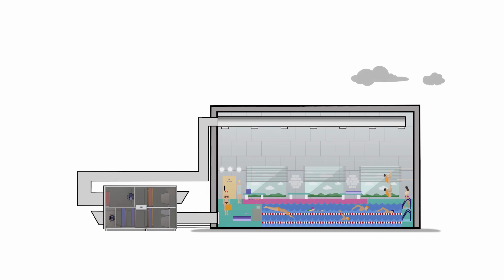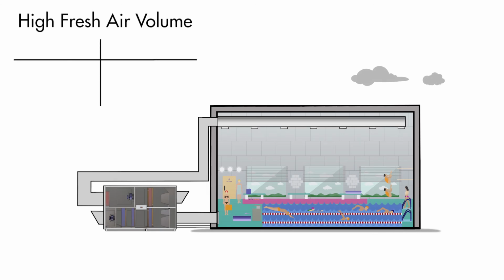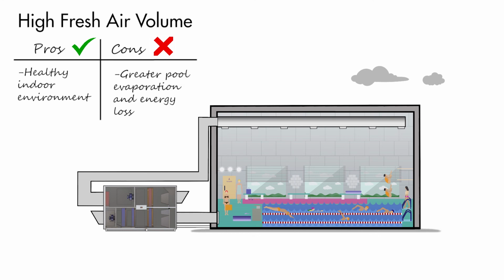Compared to many other pool design practices seen around the world, Australian building code requires greater amounts of fresh air ventilation. This is good, as it ensures lower airborne chloramine levels and a healthier indoor environment. The downside, though, is that it leads to higher evaporation rates and energy loss, as explained earlier. However, Australian building code does not prohibit a reduction in fresh air ventilation when a pool is not in use.